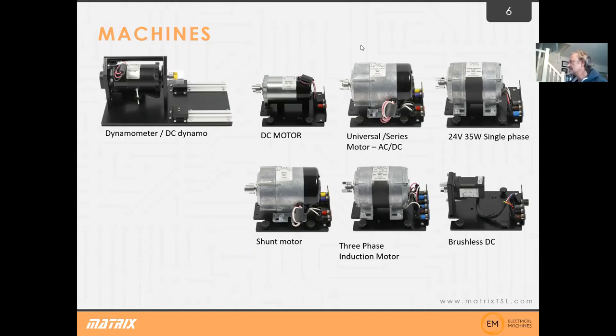There was a question about VFD within the control box - yes, it is a VFD system. VFD stands for variable frequency drive, and the machine the box creates for the induction motors produces a frequency between roughly 30 hertz and 100 hertz, exactly how VFDs work in industry. So again, it's modern electrical machines, and we're driving this with a digital signal at all times.